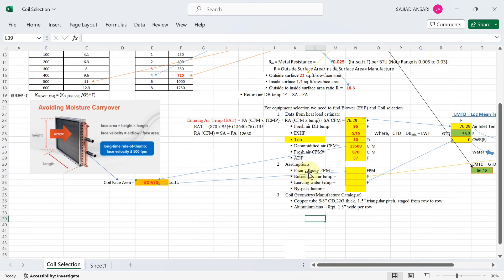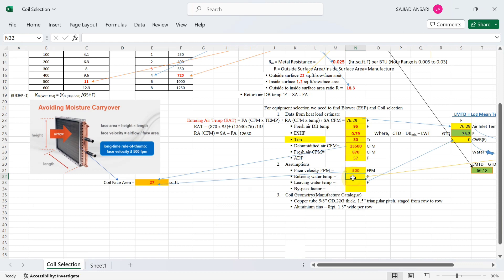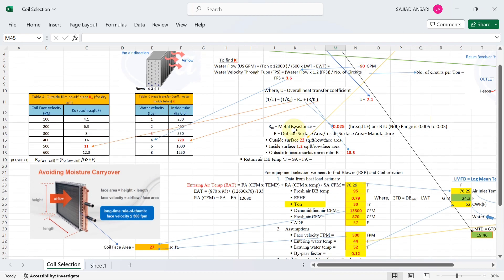Now entering the assumptions: face velocity is 500 FPM, chilled water entering temperature is 44°F, leaving temperature is 52°F, and bypass factor is 12%. From the manufacturer, metal resistance value is 0.025 per BTU, and the outside to inside surface area ratio (capital R) is 18.3.